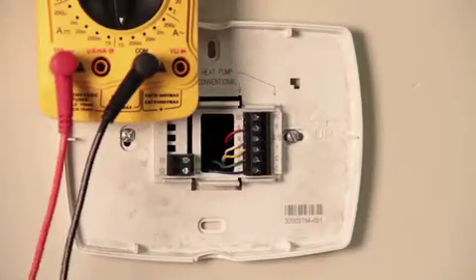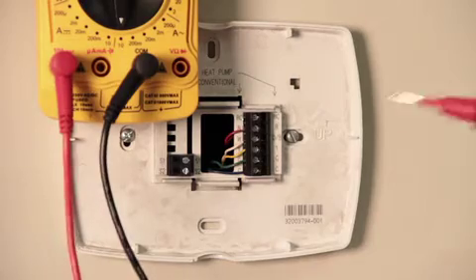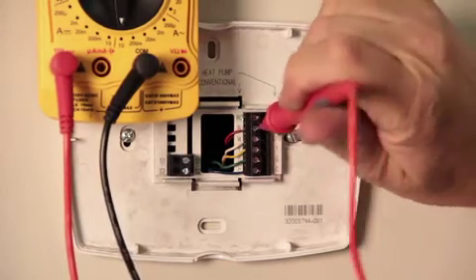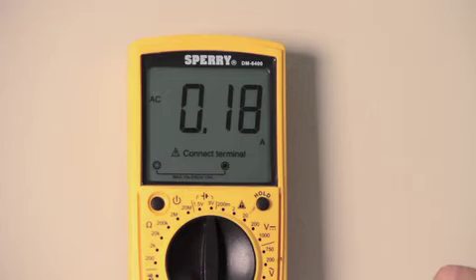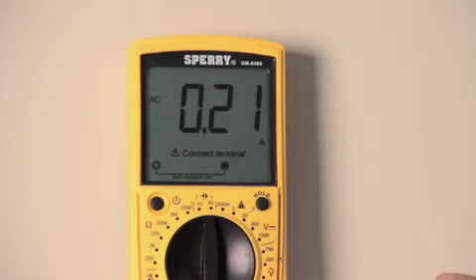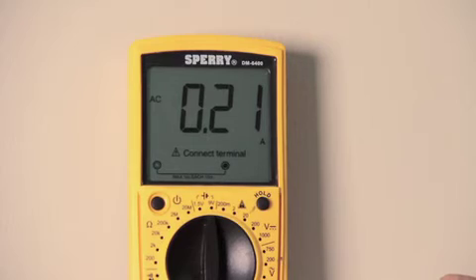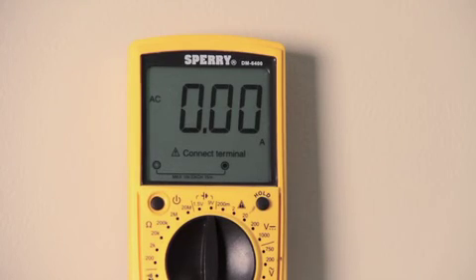As we check with an amp meter, we'll put the amp meter in series with the load. If I jumper from R to Y, my compressor comes on - you can see that I'm pulling 0.21 amps. You can use your meter as a jumper and you can read amps and troubleshoot that circuit.